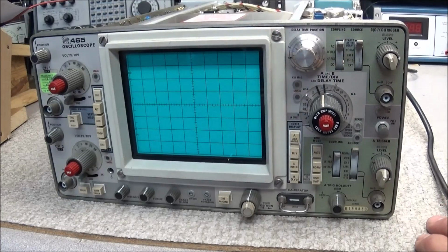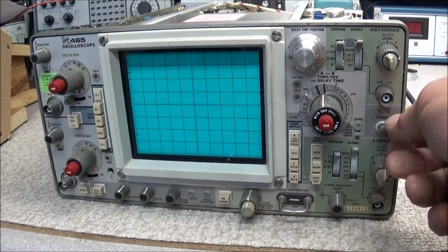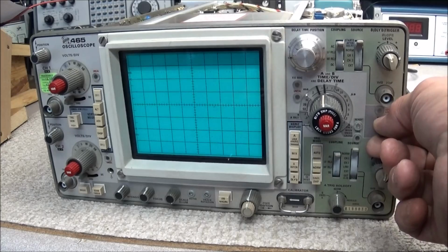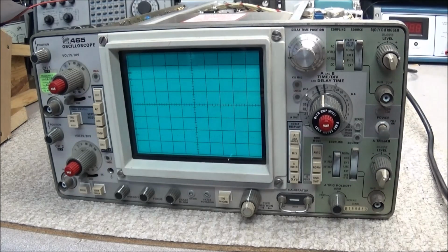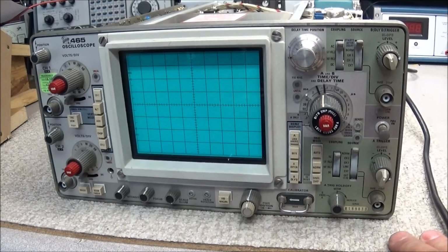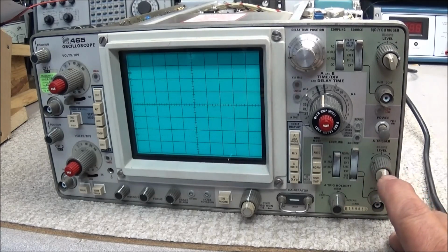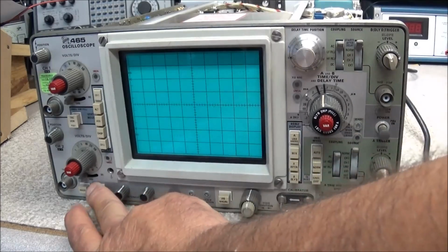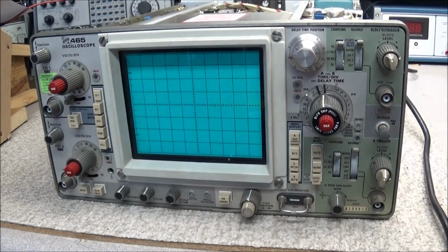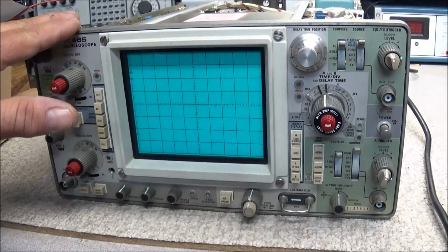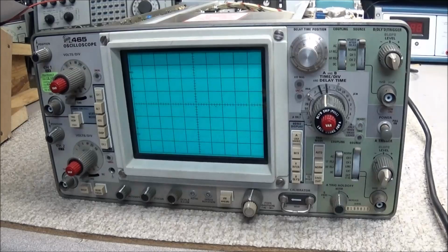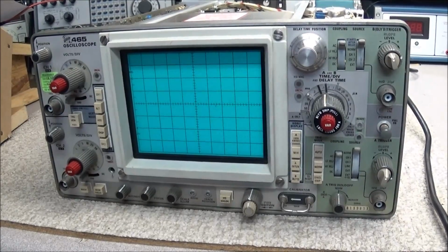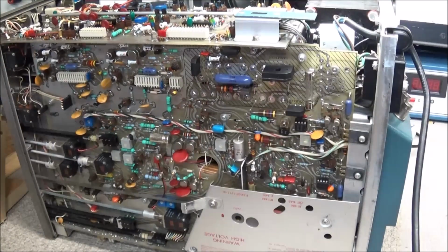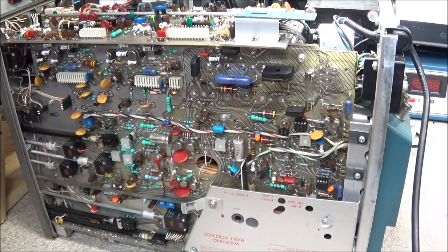Okay, so the scope is plugged into some current limiting protection, and we'll go ahead and pull the power switch on. And as you see, we have nothing. No lights. I don't hear a fan running. Nothing. We'll hit beam find just to make sure. Nothing on the screen. No trace, no dot, no power lights, no nothing. So this tells me that there's a problem somewhere in the power supply. And another good thing was there was no smoke, so we're pretty safe on that.